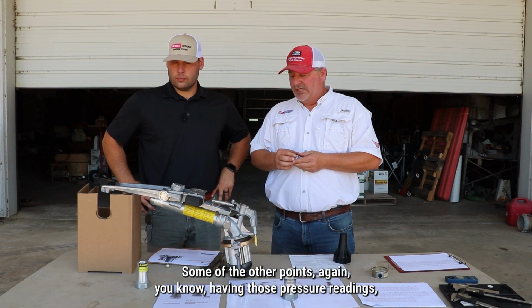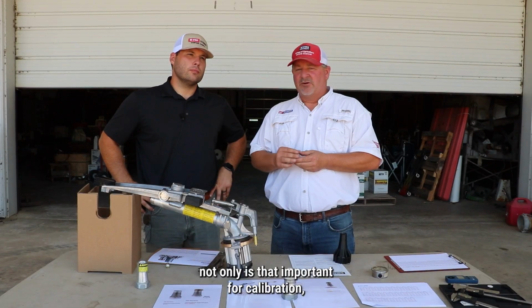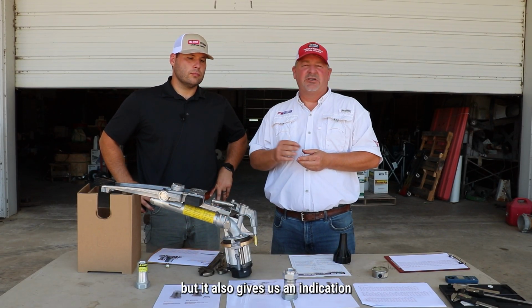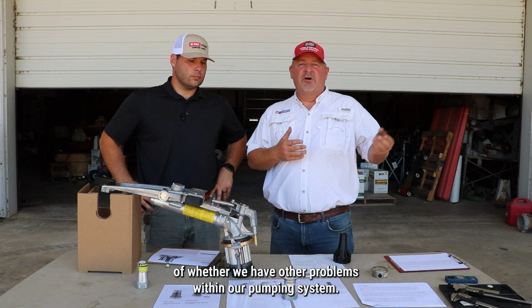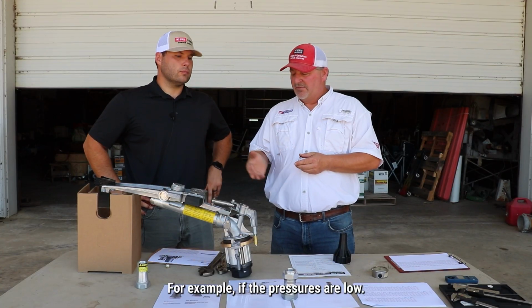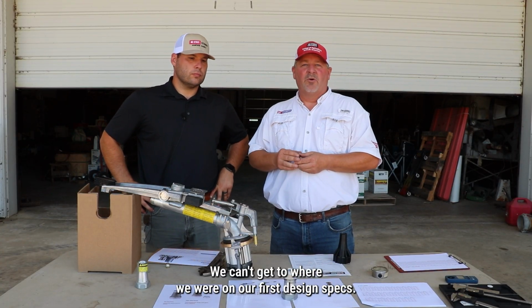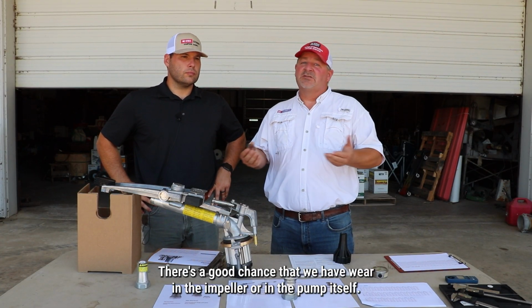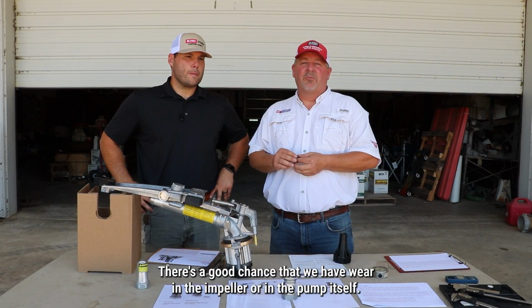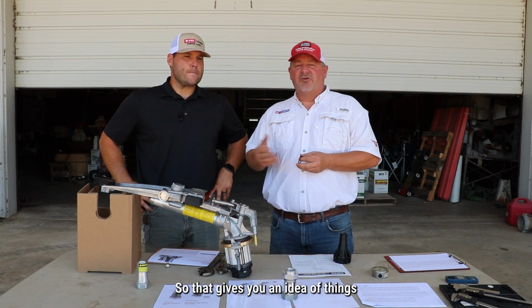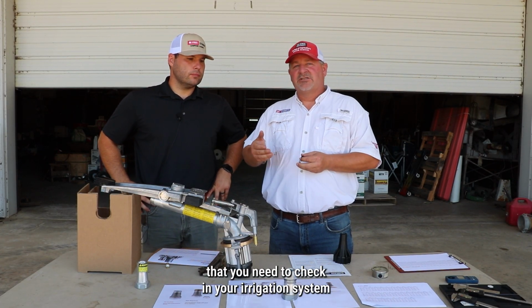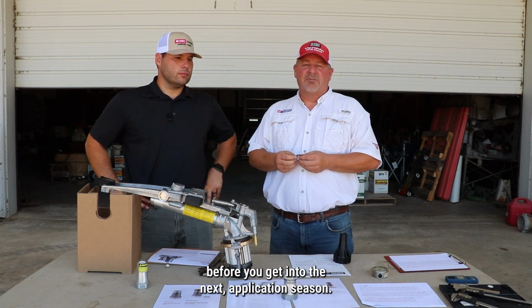Some of the other points, again, having those pressure readings, not only is that important for calibration, but it also gives us an indication of whether we have other problems within our pumping system. For example, if the pressures are low and we can't get to where we were on our first design specs, there's a good chance that we have wear in the impeller or in the pump itself. So that gives you an idea of things that you need to check in your irrigation system before you get into the next application season.